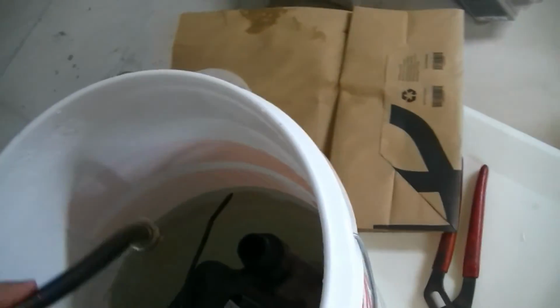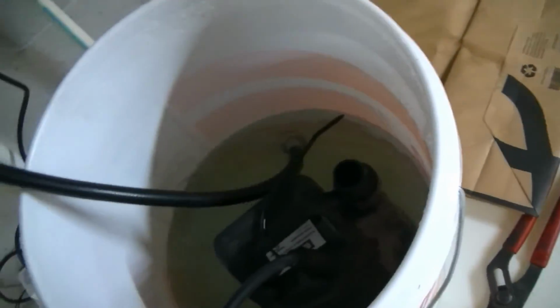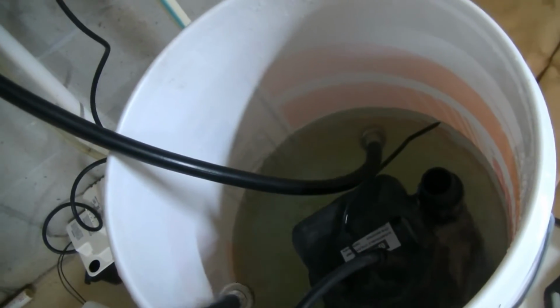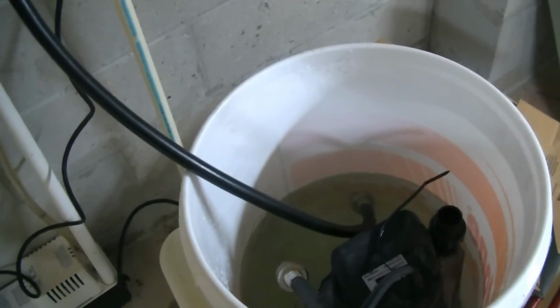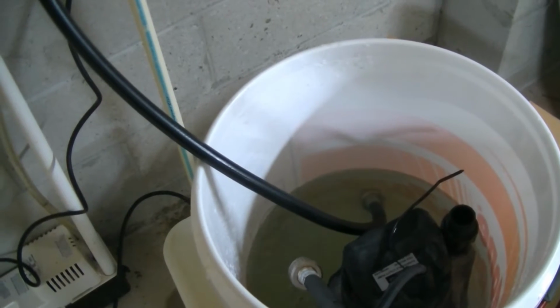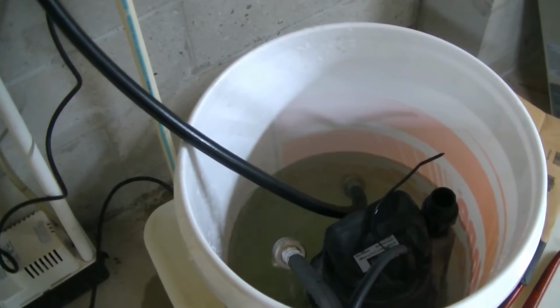And we're going to open our pressure relief again. This is going to allow all the vinegar in the tank and heat exchanger to drain out into the bucket. A little bit's going on the floor, that's okay - all it's going to do is clean the floor.